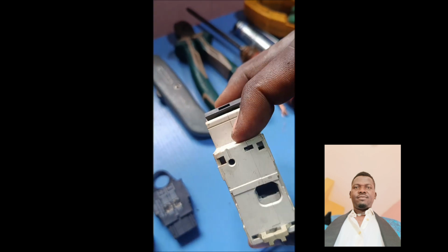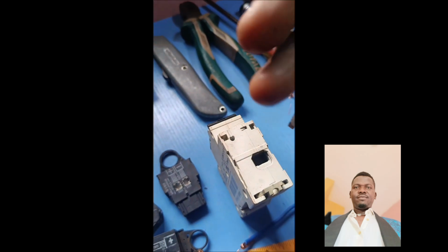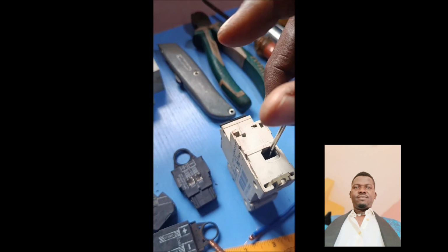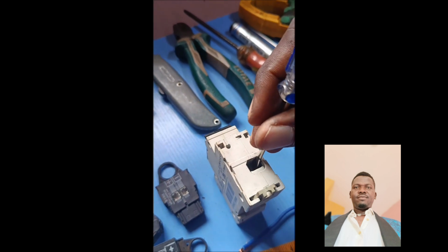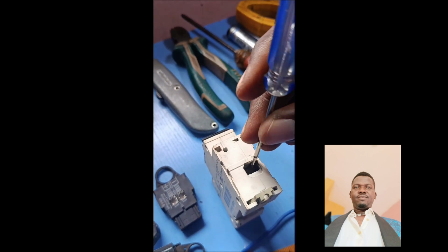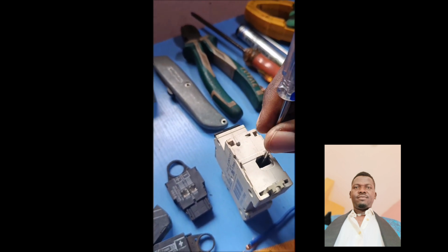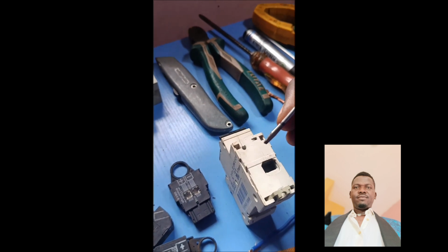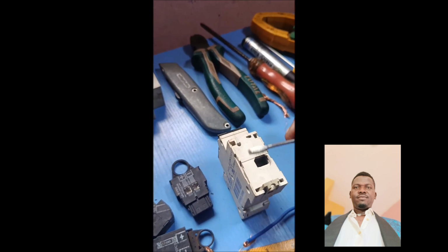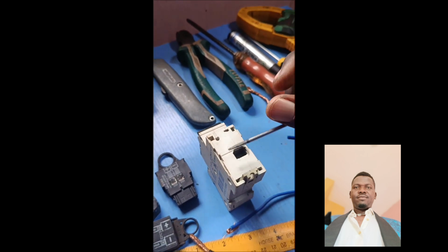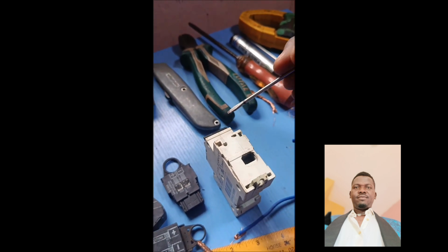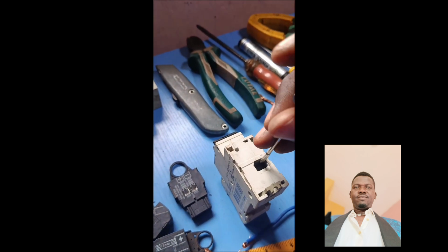So that is it. Secondly, if you want to measure, like this breaker, there is no description of the stripped length. You can use your screwdriver, or even your wire, dip in and look for the contacts. See the length. You can use something to measure it like this. Like this one already prepared, you can see a mark I gave for this demonstration.